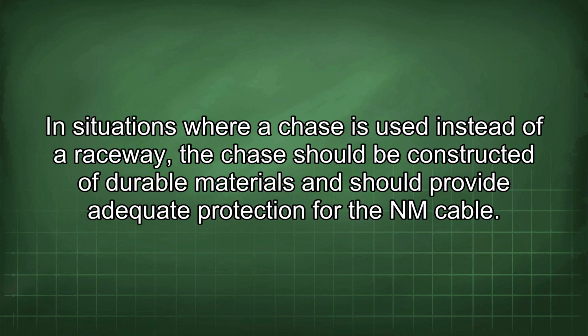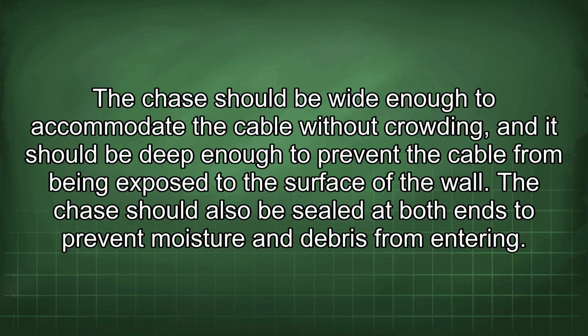In situations where a chase is used instead of a raceway, the chase should be constructed of durable materials and should provide adequate protection for the NM cable. The chase should be wide enough to accommodate the cable without crowding, and it should be deep enough to prevent the cable from being exposed to the surface of the wall. The chase should also be sealed at both ends to prevent moisture and debris from entering.